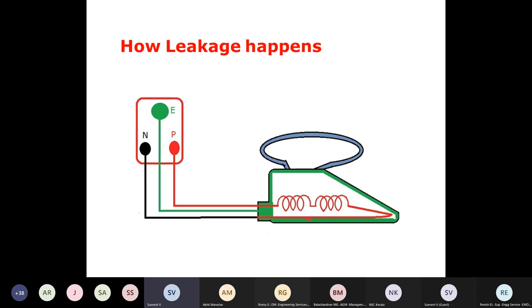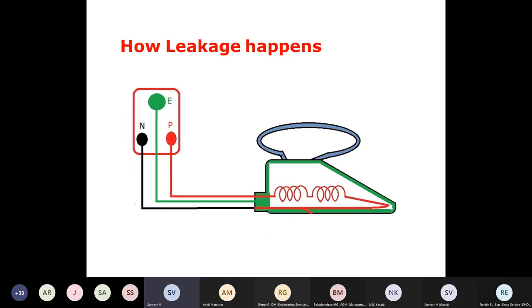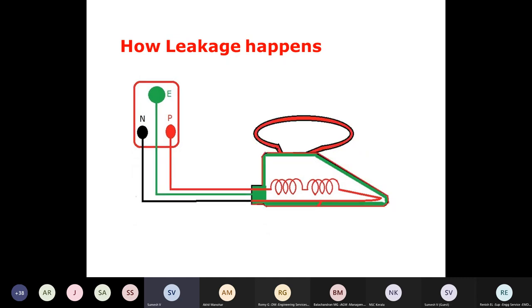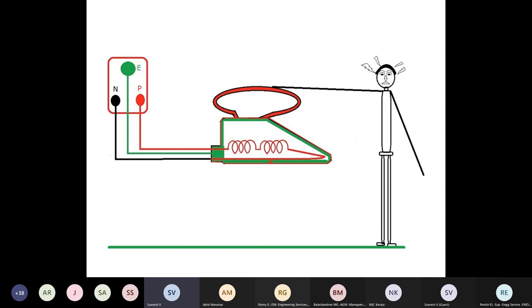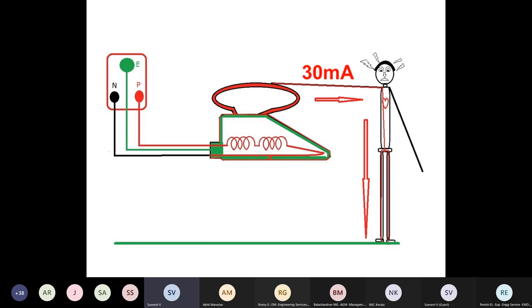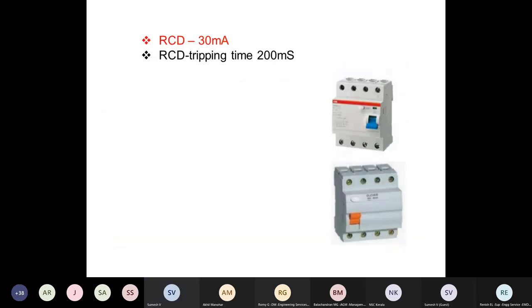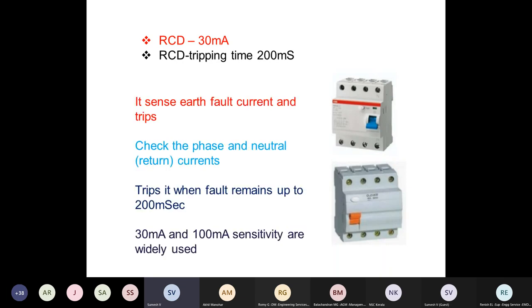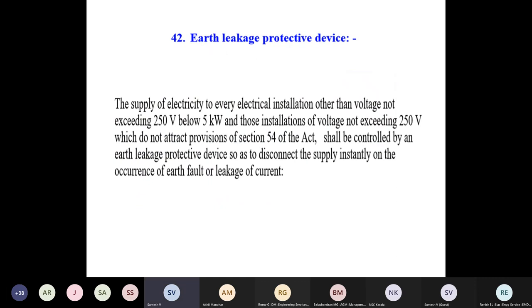But due to many reasons, that insulation may get damaged. In such a case, the supply may appear on the body of the instrument. If some person touches that body, that fault current passes through the human being, and he may get a shock. If that current is limited below 30 milliampere, it may not be fatal. For that purpose, we are using RCCB. RCCB of 30 milliampere sensitivity and tripping time less than 200 milliseconds. This is a regulated requirement.